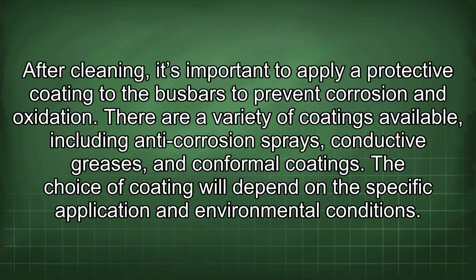After cleaning, it's important to apply a protective coating to the busbars to prevent corrosion and oxidation. There are a variety of coatings available, including anti-corrosion sprays, conductive greases, and conformal coatings. The choice of coating will depend on the specific application and environmental conditions.